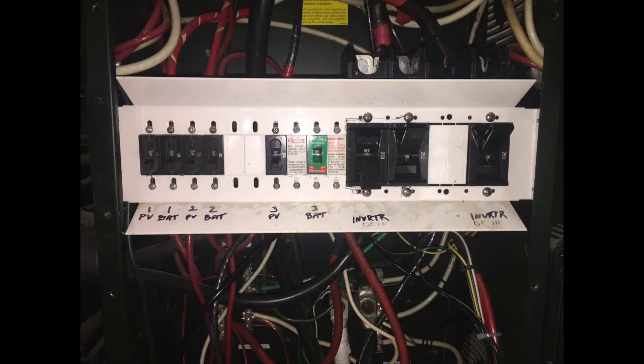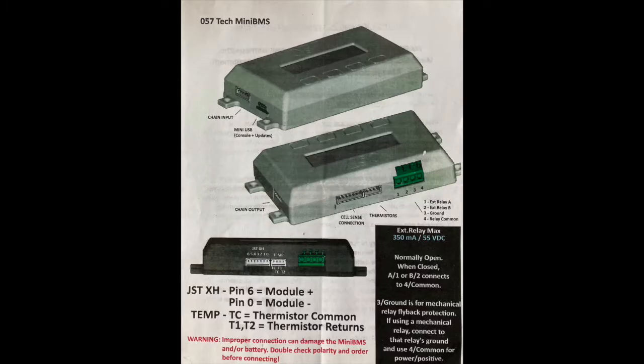Even though the charge controllers have the correct settings, I can't be sure that somebody won't someday go in and change a setting, or that a controller might fail in a particularly bad way. I set up the BMS to control all the charging and loads based on the battery voltage and temperature. If the batteries get too hot or too cold, or the voltage gets too high or too low, you end up with that bad dog at the party.